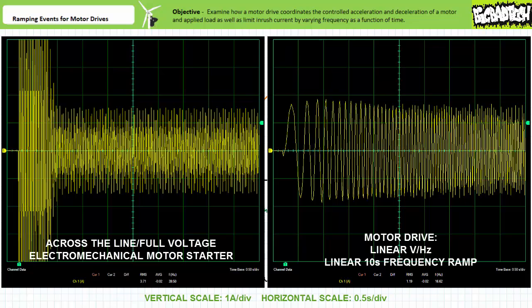Note the dramatic surge of inrush current for the electromechanical across-the-line full-voltage starter, and note the conspicuous absence of the same for the motor drive. Not only is inrush current dramatically reduced using this method, but whatever load is being driven by the gently accelerated motor isn't yanked in half.